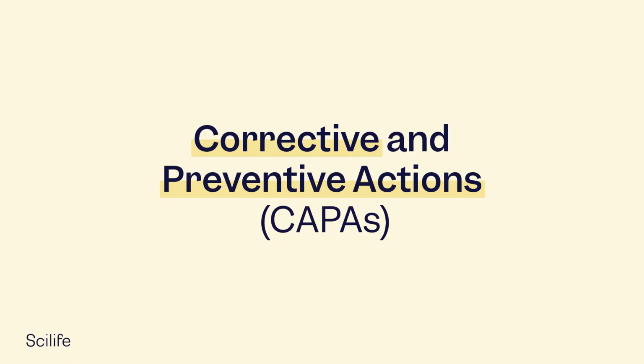Sometimes it is not possible to find the true root cause of the quality defect. In this case, you should identify the most probable root cause and address it. If there are other activities outsourced to a third party, keep in mind that you need to have a contract in place. The contract should describe the roles and responsibilities of the third party regarding the assessment, investigation, sharing of information, and implementation of CAPA actions.